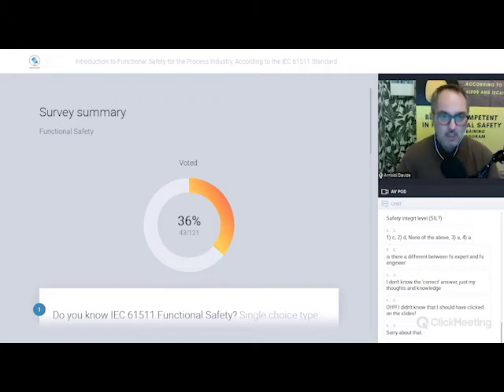Then the second point, do you know the meaning of SIL level? SIL means safety integrity level. The first answer was the SIL level is the degree of reliability of the device. The second is the SIL level is the degree of reliability of the safety loop. And the third was the SIL level is the degree of reliability of the safety PLC. PLC is the programmable logic solver, controller. So the correct answer is the second. We cannot speak about the safety integrity level for a device.